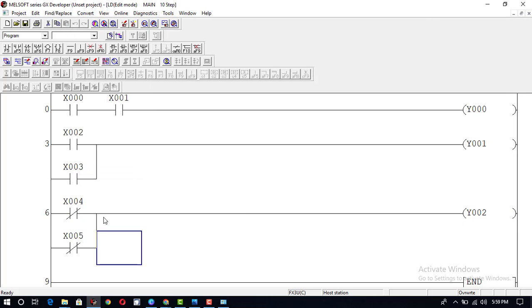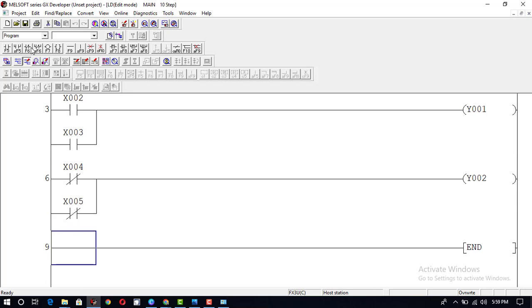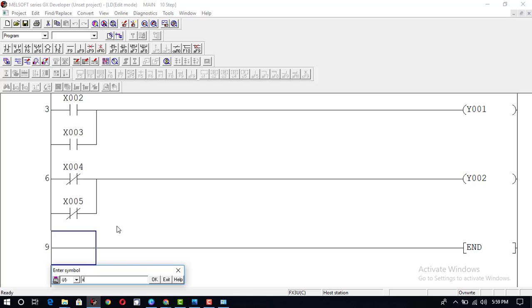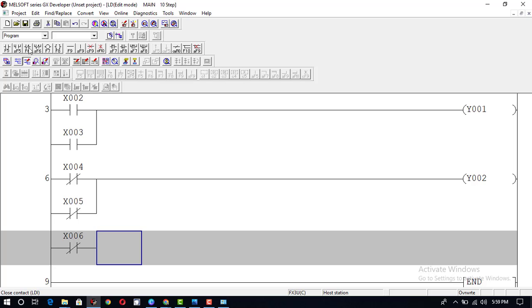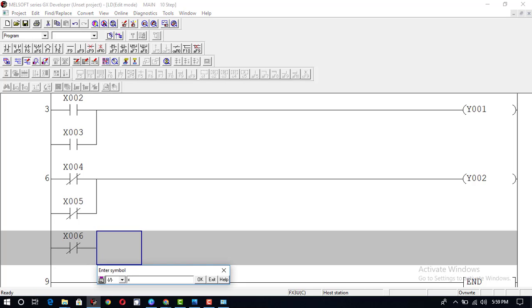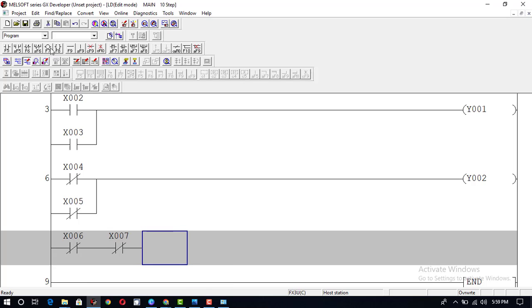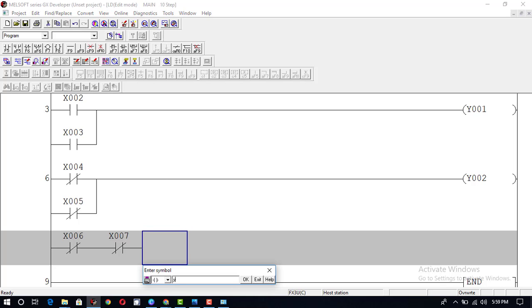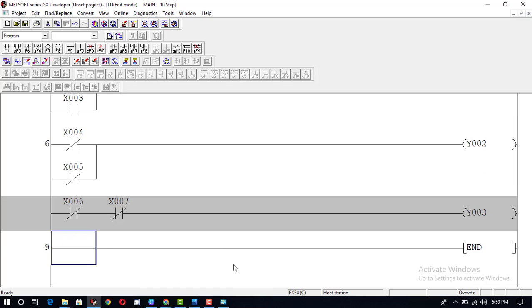Go to Write mode and here we will construct a program for the NOR gate. NOR gate is the opposite of OR gate. In OR gate both inputs are in parallel; in NOR gate both inputs will be in series and in normally closed condition. So we will take normally closed inputs X6 and X7, both in series, and here Y3 is the output. This is our NOR gate.